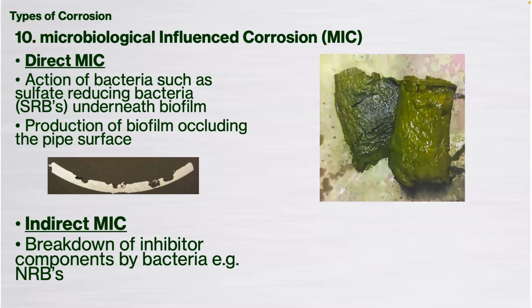But just to give you an idea, and it's a pretty disgusting picture, this is actually from a military base in upstate New York. This is one of our X-Pot compact filters. It's a cartridge filter underneath all that, would you believe? And that's biofilm, the slime that I was talking about. We removed this using a non-flush cleansing agent, which strips the biofilm, and we killed the bacteria through pasteurization in this particular case. But yeah, this stuff's lurking in the system, and this is what happens when we don't monitor for bacteria, and the temperatures are at the right levels to support bacterial growth and proliferation.